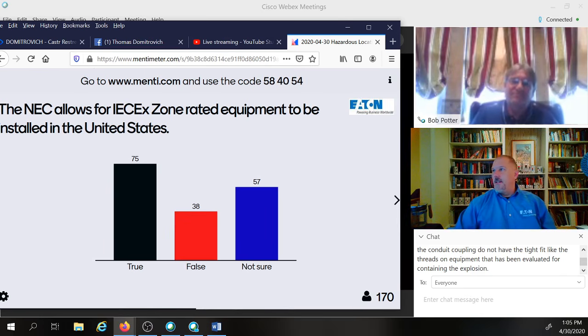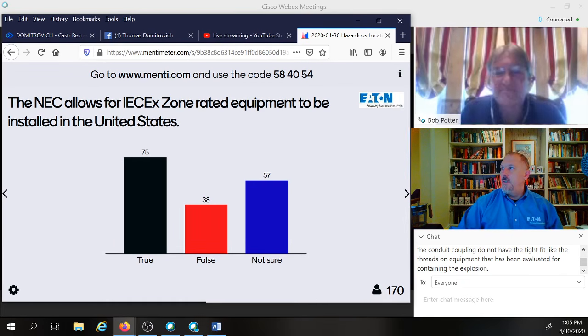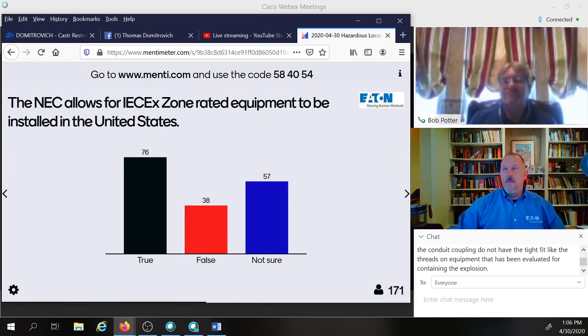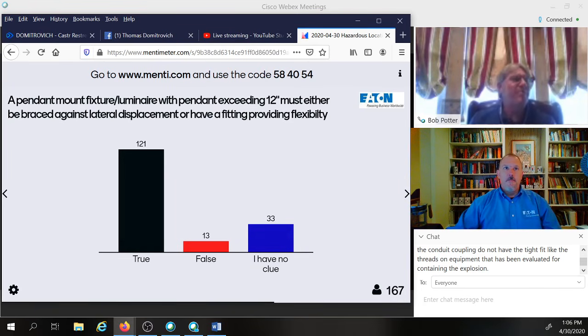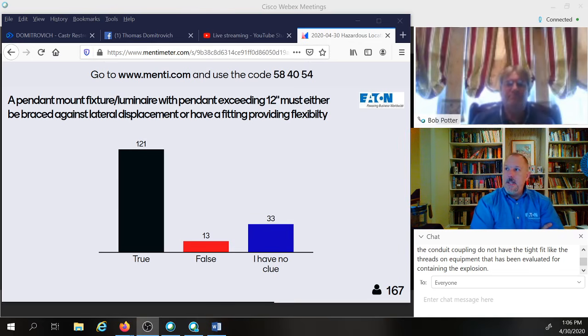All right, we're going to do the next one. So what I did was I moved the Mentimeter thing so the guys on the web can see it. I forgot I'm projecting, so I can do that. Yeah, that last question could be a case where maybe I could have worded it slightly better. That's fine. Okay, so this one here, we've got 121 say true, 13 say false, and 33 have no clue. And the question is, a pendant mount fixture luminaire with pendant exceeding 12 inches must either be braced against lateral displacement or have a fitting providing flexibility. Is it true? Is it false?